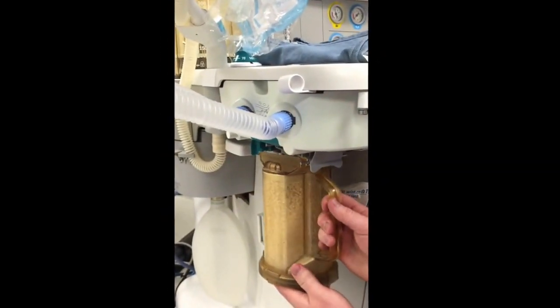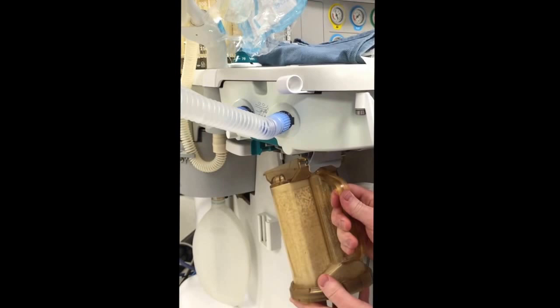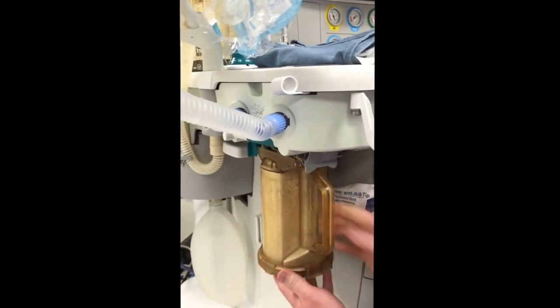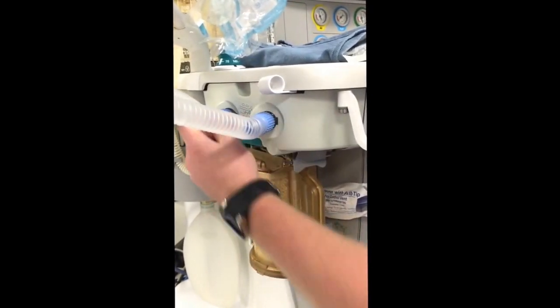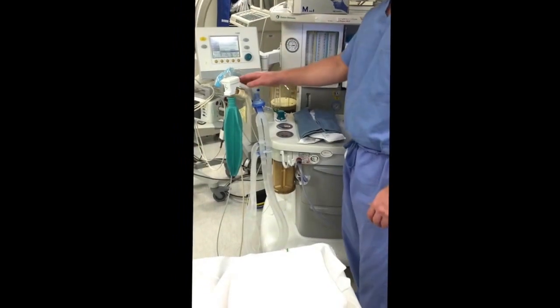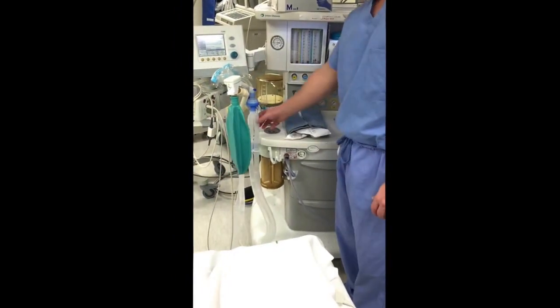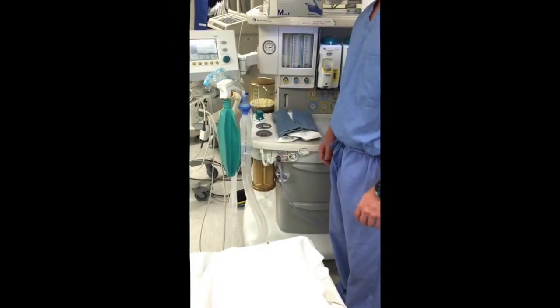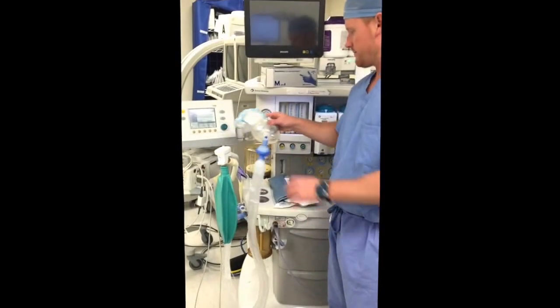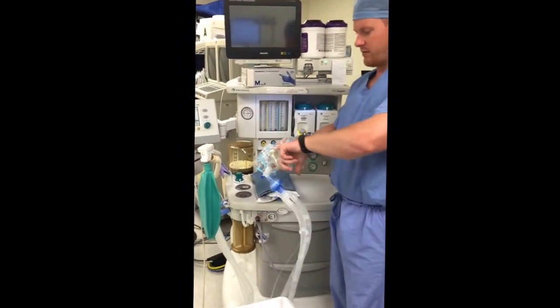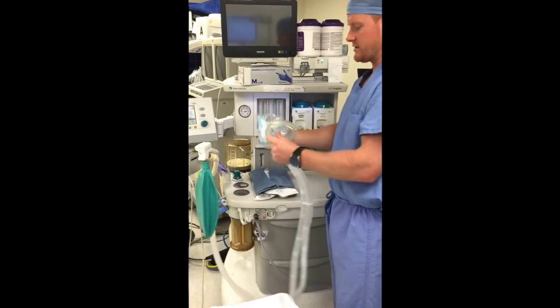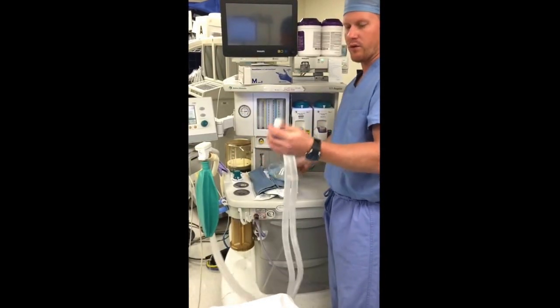Replace your CO2 absorbent. Make sure it's tight, because you don't want to leak in your system. The next thing I would do is fill my circuit and make sure that there's no leak. Some people like to hold in here. I just take the mask off and I hold it at the Y piece.